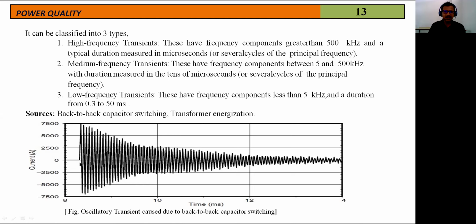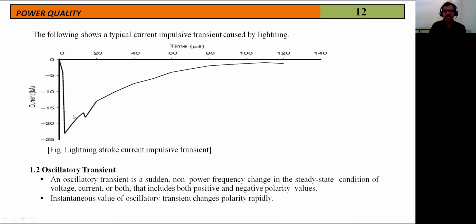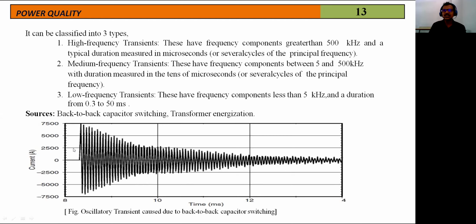Initially there are more oscillations, and as time increases the oscillations reduce. After 10 to 12 milliseconds, the oscillations have completely vanished, and we can see the normal actual current wave. Between 8 to 12 milliseconds, where the capacitor bank is switched, you can see the surge or transient in both the positive direction as well as the negative direction. This is called oscillatory transients. The earlier figure showed impulse transients, where the magnitude increases only in a particular direction, either positive or negative, whereas in an oscillatory transient the magnitude changes drastically and rapidly in both the positive as well as the negative directions. This is about transients.